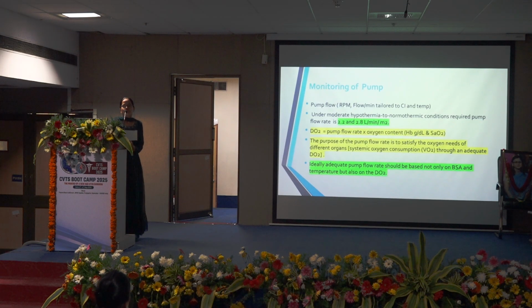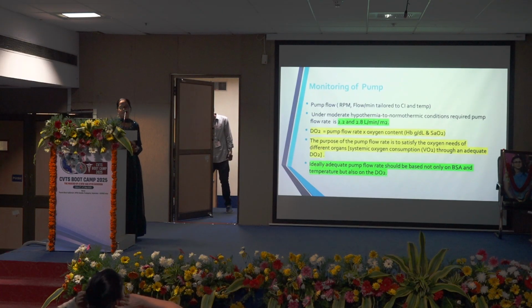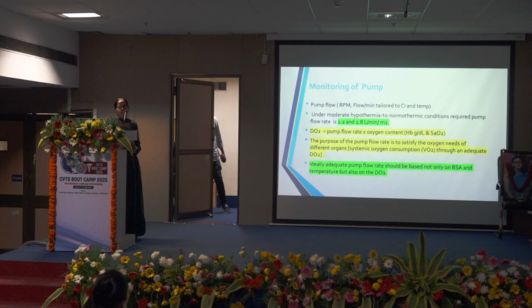So monitoring on the pump, you will be able to see the pump flow, which will basically be the revolutions per minute, and which will be tailored to the cardiac index of the patient, that is basically the body surface area, and according to the temperature. Under moderate hypothermia or normothermic conditions, the required pump flow is between 2.2 to 2.8 liters per minute per meter square. Basically the purpose of the pump is to satisfy the oxygen needs of the different organs, the systemic oxygen consumption, through adequate pump flow, that is the DO2. So the DO2 is the pump flow rate times the oxygen content, which basically depends upon the hemoglobin as well as the saturation. So ideally the adequate pump flow should be based on the body surface area, temperature, as well as the DO2.